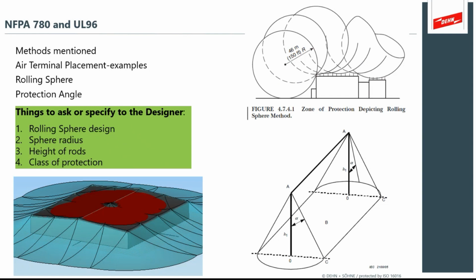And so it's using a great body of anecdotal evidence to issue guidelines on where to apply the air terminals for a likely attachment point on a structure. We also have things like the protection angle that can be used with masts, isolated masts, and catenary line type systems, where we can predict the protected volume underneath a tall mast. You often see these at things like grid switching stations and the NASA launch site type applications, where you have a mast that provides a protected volume.